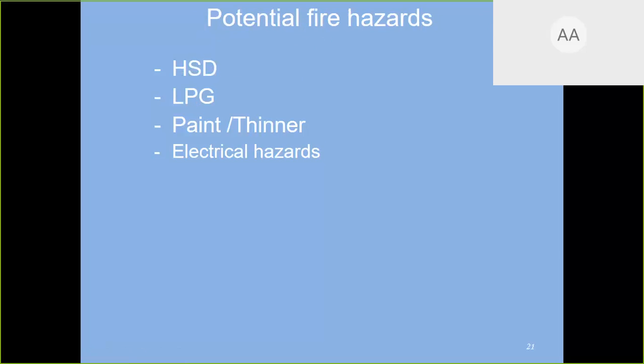Right? At each usage point, we should install the LEL detector. Each usage point, not only where we are storing. Where we are using the outlet coming off the LPG, there we should install an LEL detector as well as at the storage. Third is the paint and thinner. This is also more prone to fire hazards. What should we do for the thinner and for the paint? For paint and thinner, we have a UV IR sensor and automatic dumping of CO2, which I will cover in the next session. Okay, so please remind me, that is known as CO2 dumping for the paint and thinner. Automatic CO2 dumping. I will cover that.